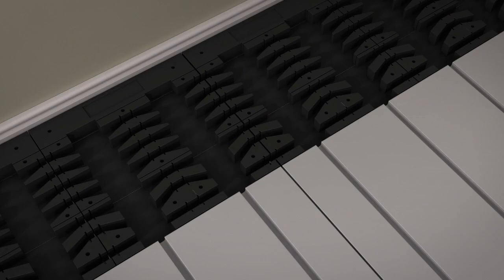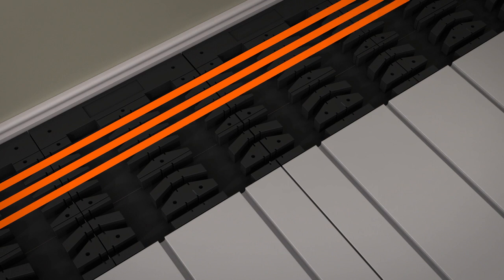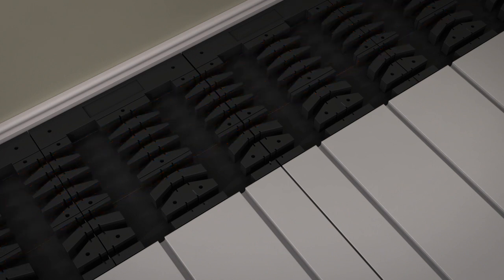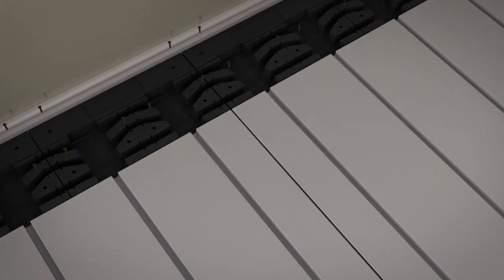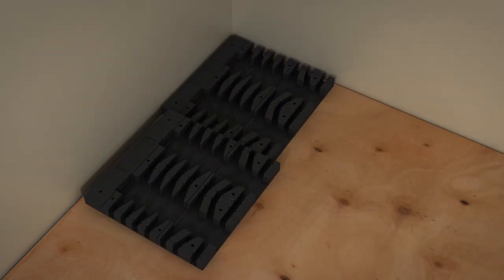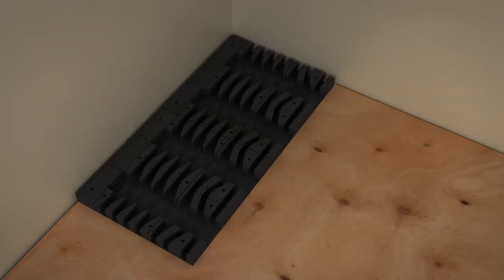The ProWarm Overlay End Returns have several unique snap-off points that accommodate for up to five runs around the perimeter. If the design only requires one or three pipe runs, simply snap off the panel to suit. These can then be fixed down using screws and suitable fixing plugs where fixing to screed. Whilst referring to your plan, begin by laying two end supports in the position you intend to start laying the boards. Fix these to the floor using screws and plugs if needed.